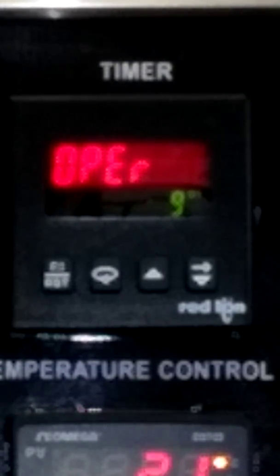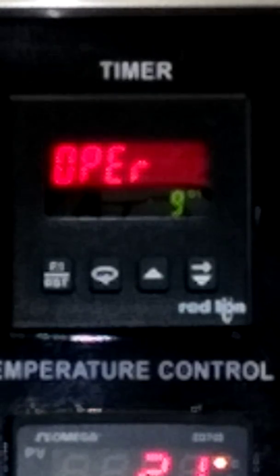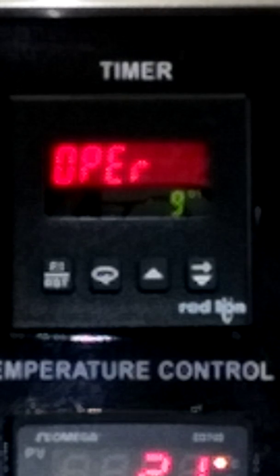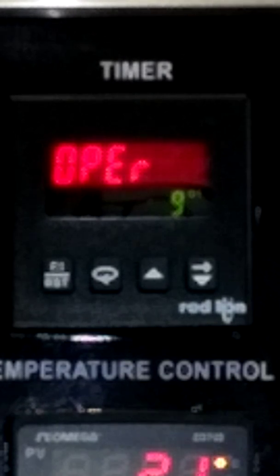The operation mode — the timer operating mode — depends on what your application is. In the manual there will be a chart and you can pick what's best for your application. Generally we do nine, which stops timing, and manual reset to zero, which means it won't reset until you hit the reset button, with a latched output.